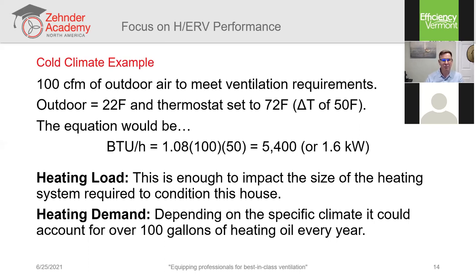Depending on how much of the year is at these cold temperatures, this ventilation energy penalty could account for over 100 gallons of heating oil — a significant cost. For a hot climate example with 100 CFM, at 92°F outdoor and 72°F indoor, the ΔT is only 20 degrees. Running the equation gives just over 2,000 BTUs per hour, or 633 watts. Summertime is definitely easier than winter in a cold climate, but it could still account for hundreds of dollars in extra electricity.